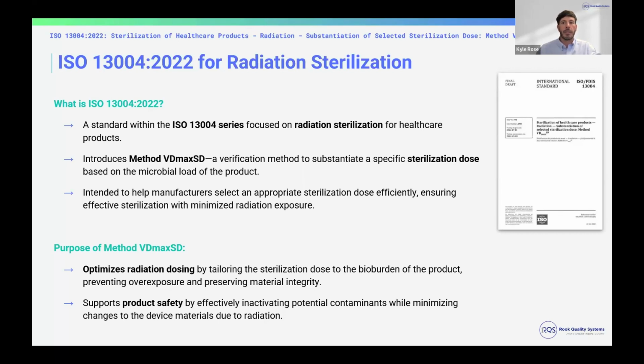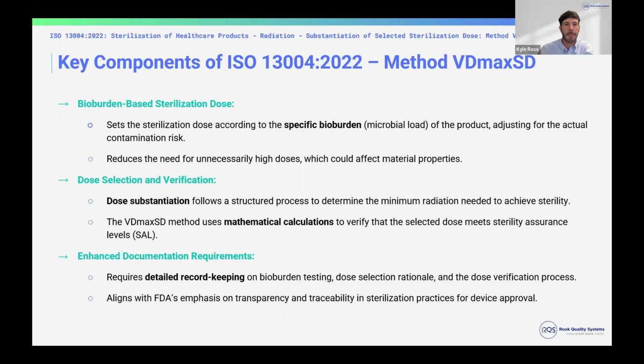So once you're using this radiation method to validate sterilization of your product, you need to identify this VD max SD and then verify that going forward with future sterilization cycles. The purpose of this is to optimize radiation dosing. So you're tailoring this dose to the bioburden of the product, preventing overexposure or under-sterilization for this device. It supports product safety by effectively inactivating contaminants while making sure the devices aren't damaged with more radiation than's needed, right? So that's the main focus of identifying and validating this process.